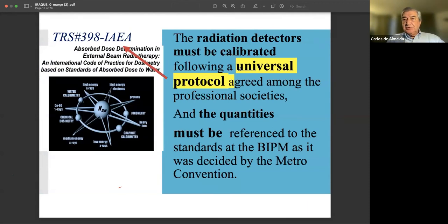In order to do that, what we should do is to use a protocol or some code of practice like the one that the IAEA proposed in 2010 and that is also being upgraded recently. When we say using a universal protocol, it means that we must use the same reference conditions: the distance from source to the surface of the phantom, the field size, and the depth where we place ion chambers. This is called the reference condition. This is the condition for which a calibration lab would provide you a calibration coefficient, and that's the reference condition that you should use in your institution. And the quantity that you are measuring, in this particular case absorbed dose, must be referenced to the standard of the BIPM, as was decided by the Metre Convention.